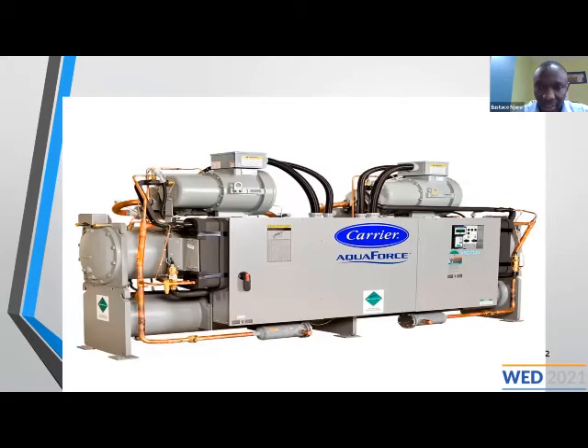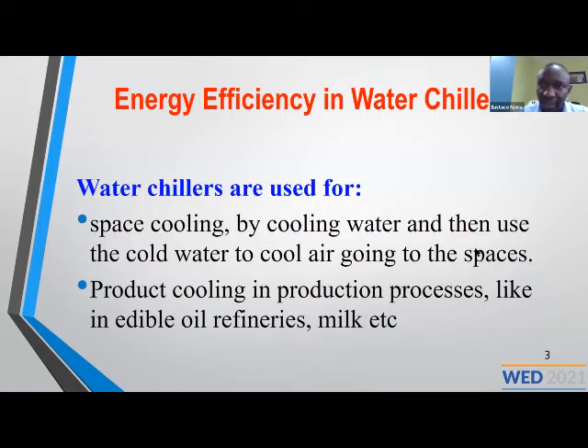And without wasting time, that's how a chiller looks without being connected to any other system. And this one is our water-cooled chiller. As we have seen, chillers are used in cooling water, and that water is cooled for product cooling, either in manufacturing or in space cooling. You find them in oil refineries, you find them so much in milk factories and data processing centers. Especially in Kenya, now that we are embracing a lot of IT, many people are going to be setting up data processing centers and servers which are required to maintain a certain temperature. And the chillers come in handy in that.